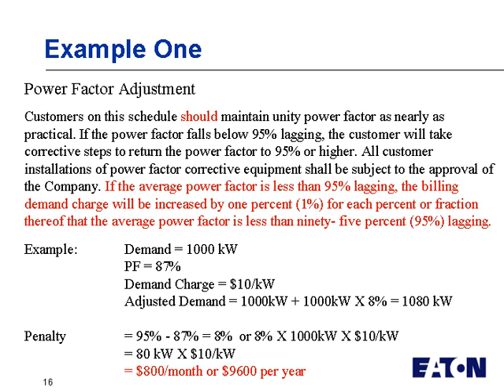This first example is, again, taken right out of the tariff, and I think the most interesting thing on this one says, the customer on this schedule should maintain unity power factor, which means very efficient use of power. But they say anything below 95%, if the average power factor is less than 95% lagging, the billing demand charge will be increased by 1% for each percent or fraction thereof that the average power factor is less than 95%.